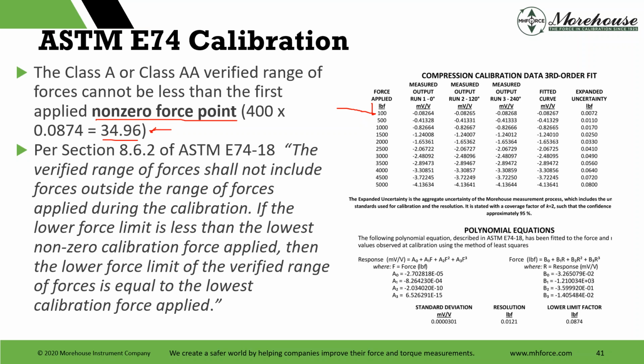E74 is clear on this. The verified range of forces shall not include forces outside the range of forces applied during the calibration. If the lower force limit is less than the lowest non-zero calibrated force applied, then the lower force limit of the verified range of forces is equal to the lowest calibration force. That's what's happening right here. Here's that standard deviation that we're getting from that formula, 0.0000301 millivolts. Convert that to pounds, and we get that.